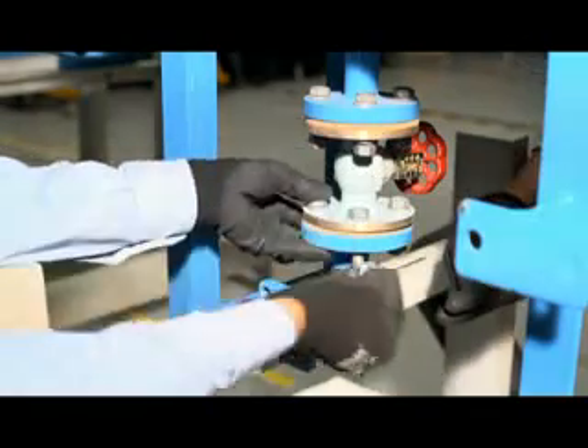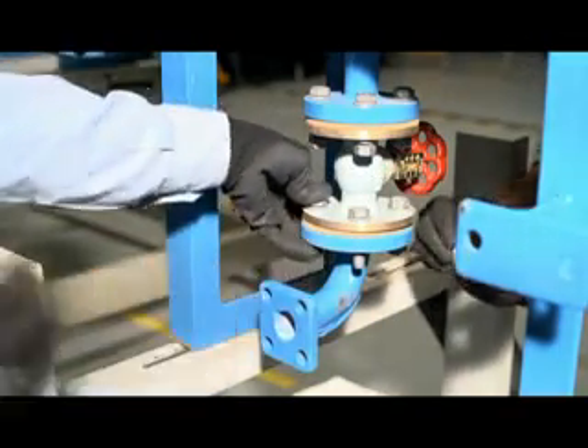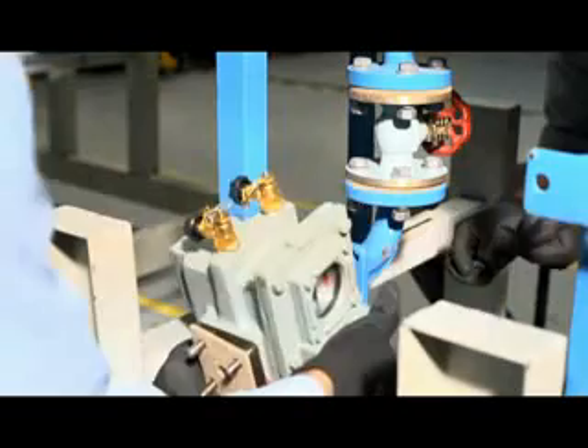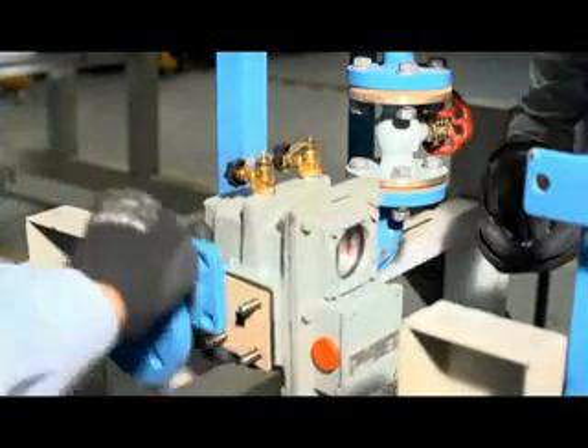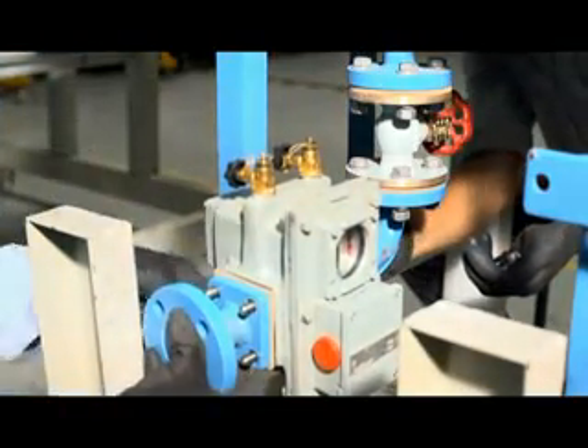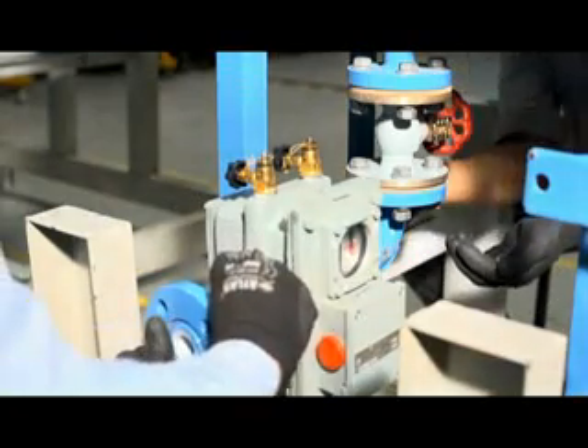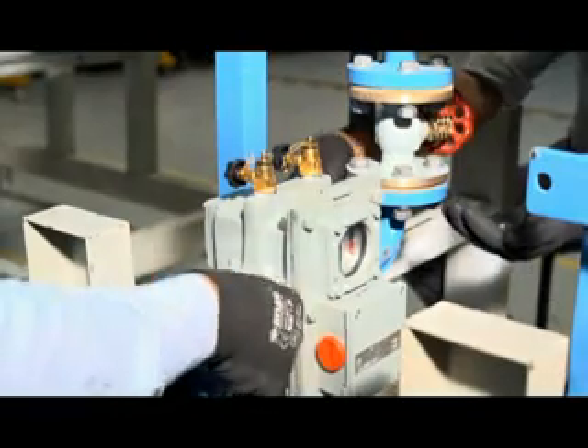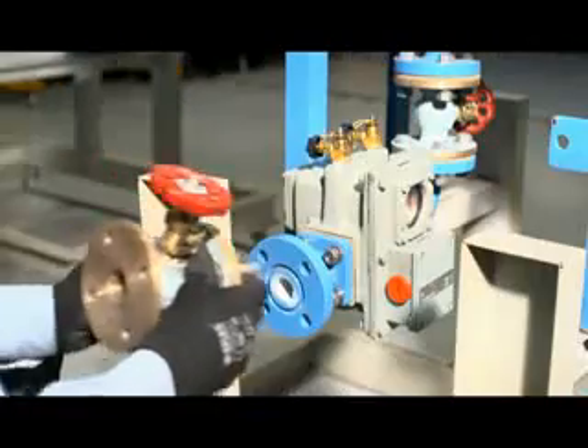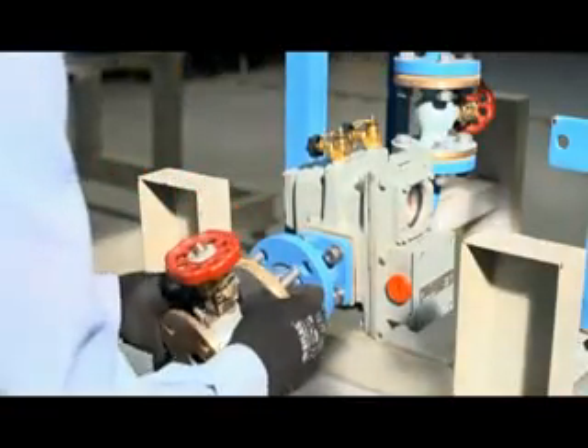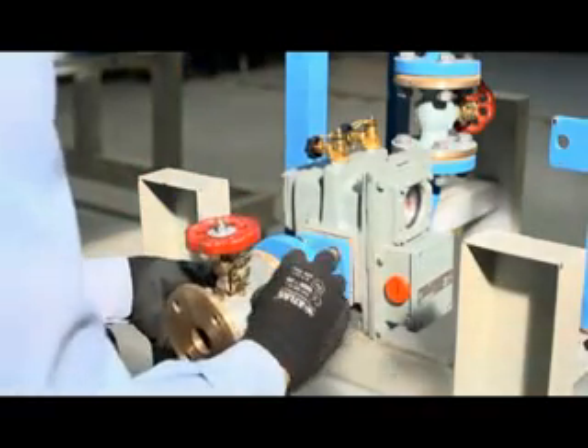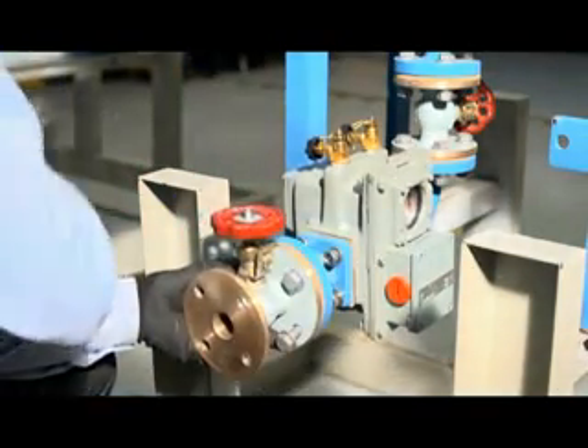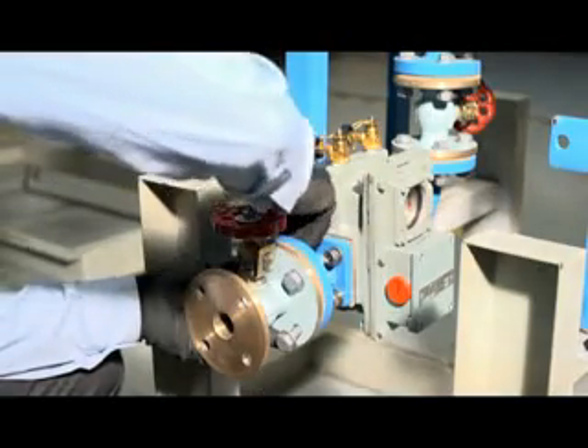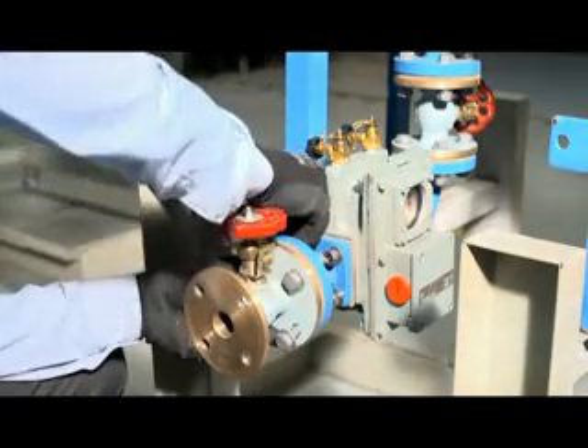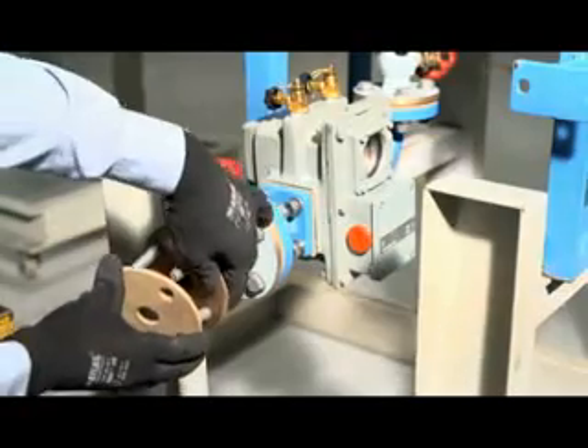A conservator tank of a transformer provides adequate space to the expanded transformer oil. It also acts as a reservoir for transformer insulating oil. This is a cylindrical shaped oil container closed from both ends. One large inspection cover is provided on either side of the container to facilitate maintenance and cleaning inside of the conservator. The conservator pipe, that is, the pipe that comes from the main transformer tank, is projected inside the conservator from the bottom portion.